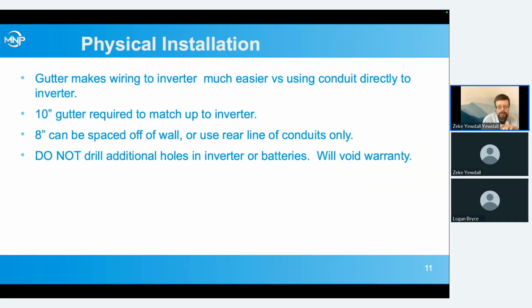Installation: using a gutter, also called an electrical trough or electrical wireway, makes wiring to the inverter much easier versus using conduit directly to the inverter. All the knockouts are on the bottom of the inverter, which often ends up with a whole bunch of flex conduit or LBs, things sticking off the bottom for all the different things. You've got DC from your PV, DC from your batteries, AC from a variety of different sources and outputs. There can be a lot of stuff sticking off the bottom of that inverter, and using just one gutter under there can make it look a lot cleaner and a simpler installation.